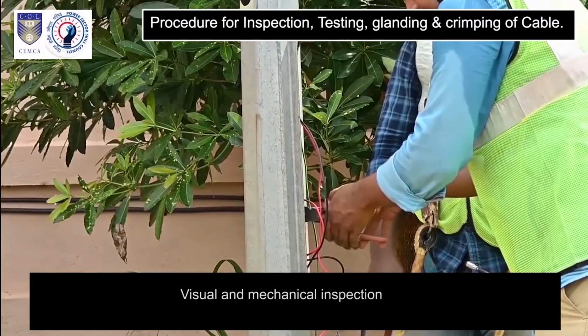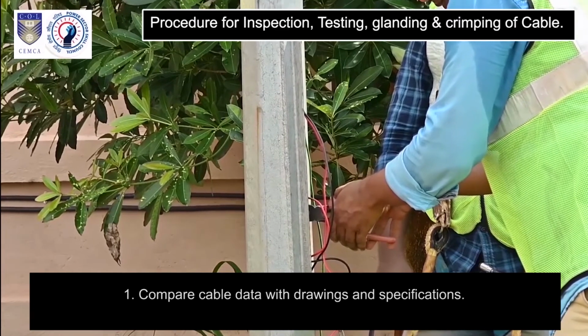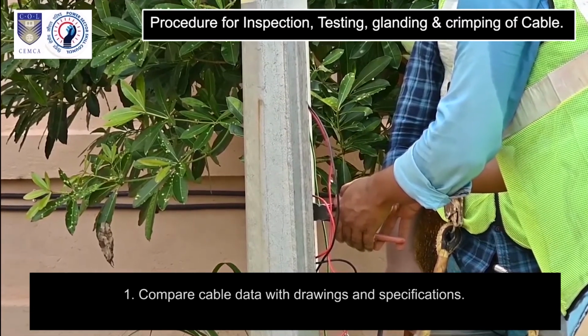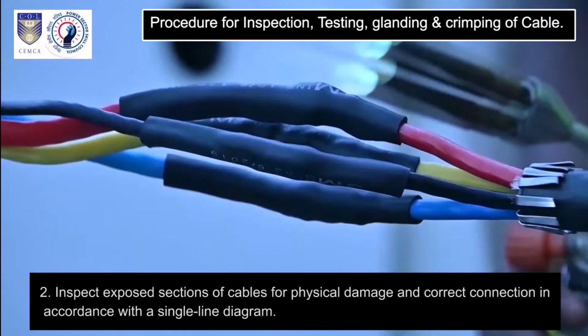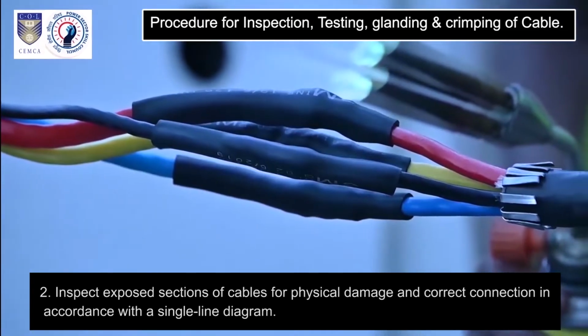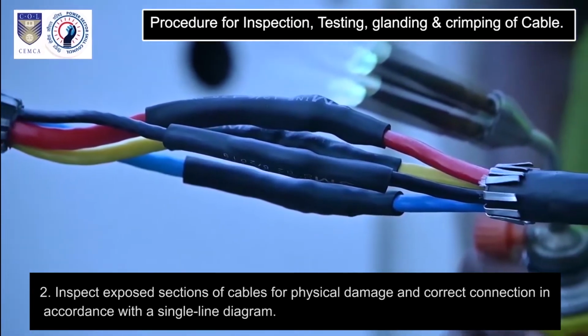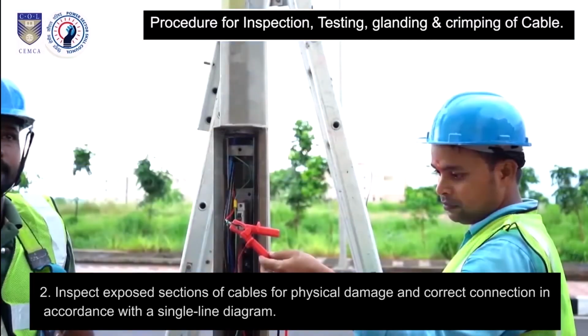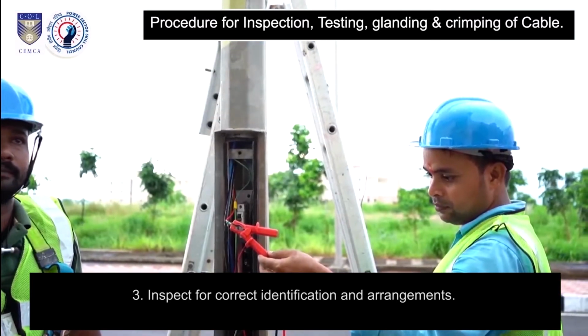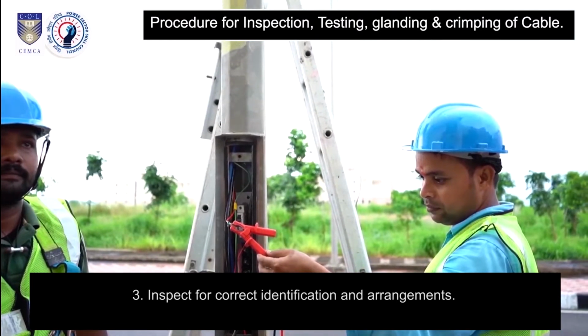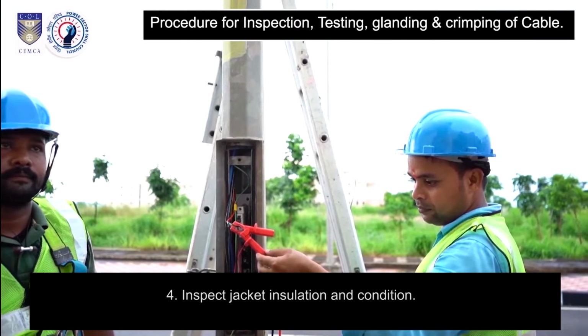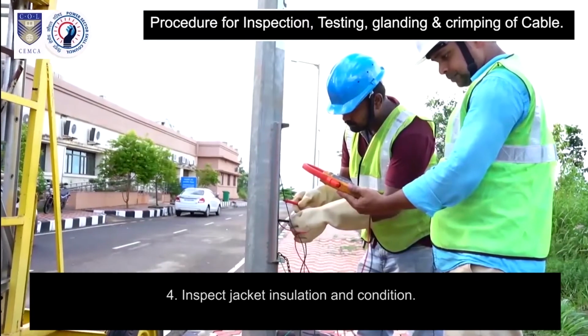Visual and mechanical inspection. 1. Compare cable data with drawings and specifications. 2. Inspect exposed sections of cables for physical damage and correct connection in accordance with a single line diagram. 3. Inspect for correct identification and arrangements. 4. Inspect jacket insulation and condition.